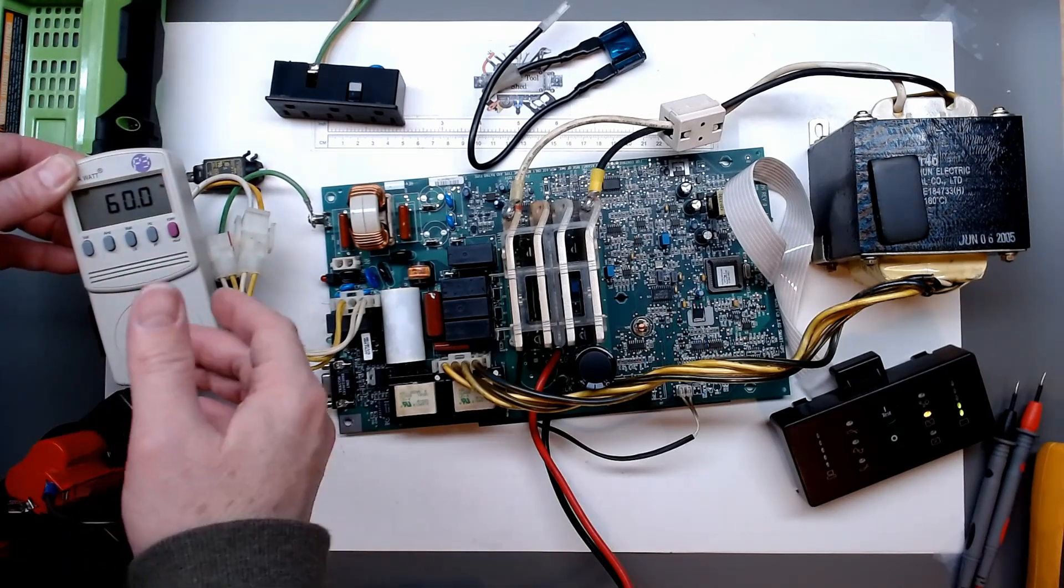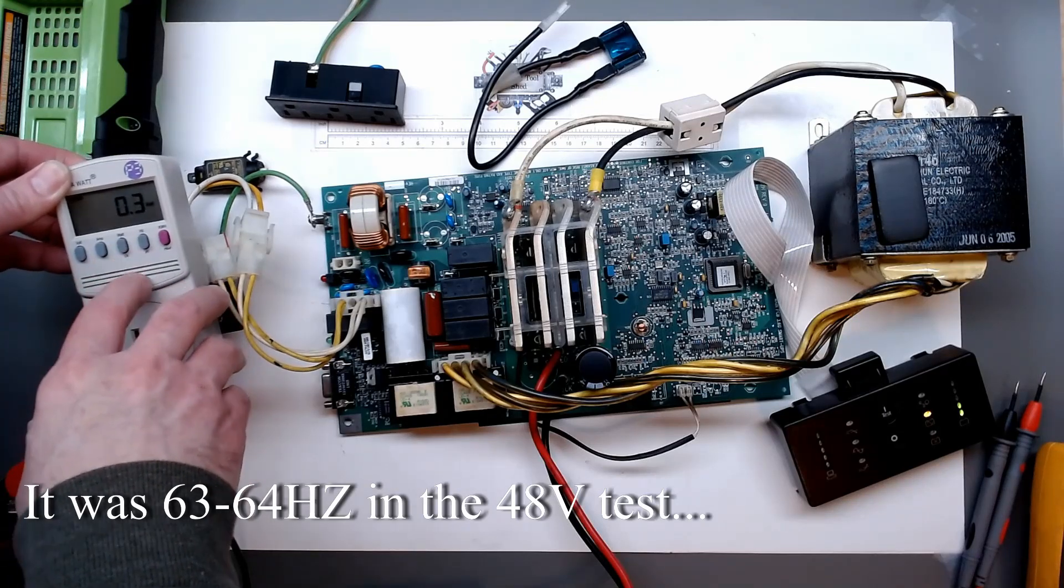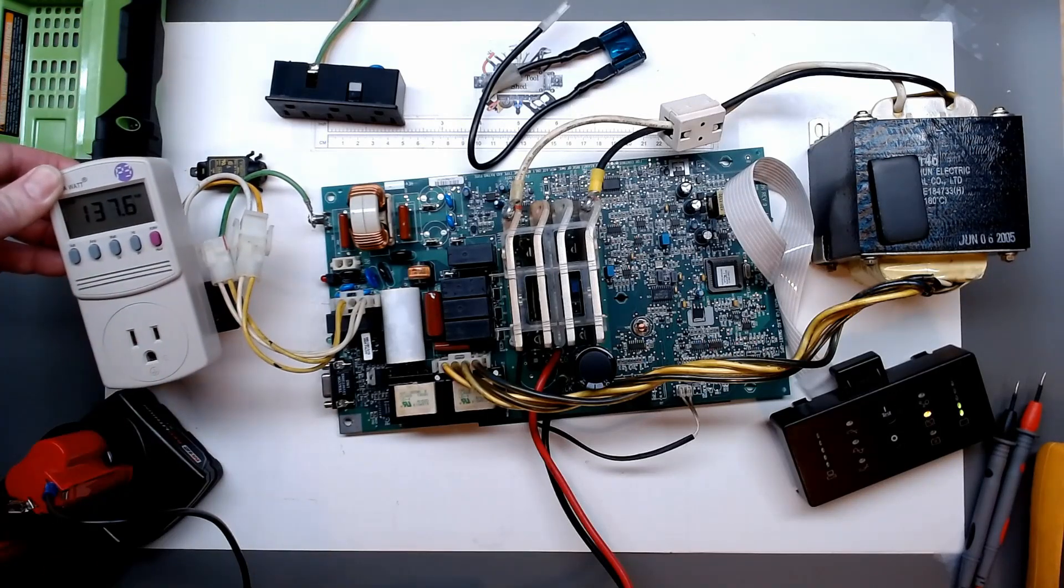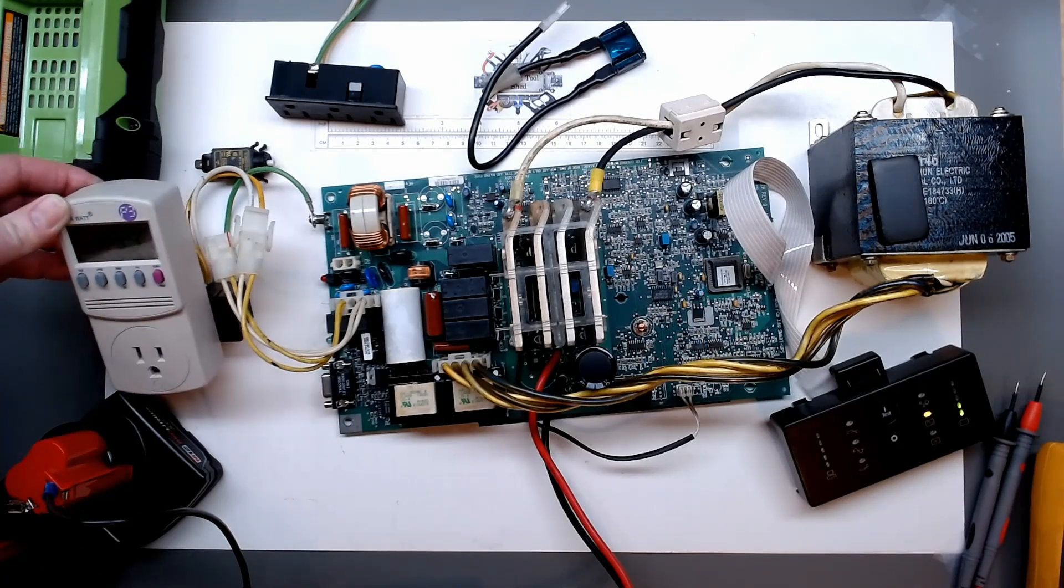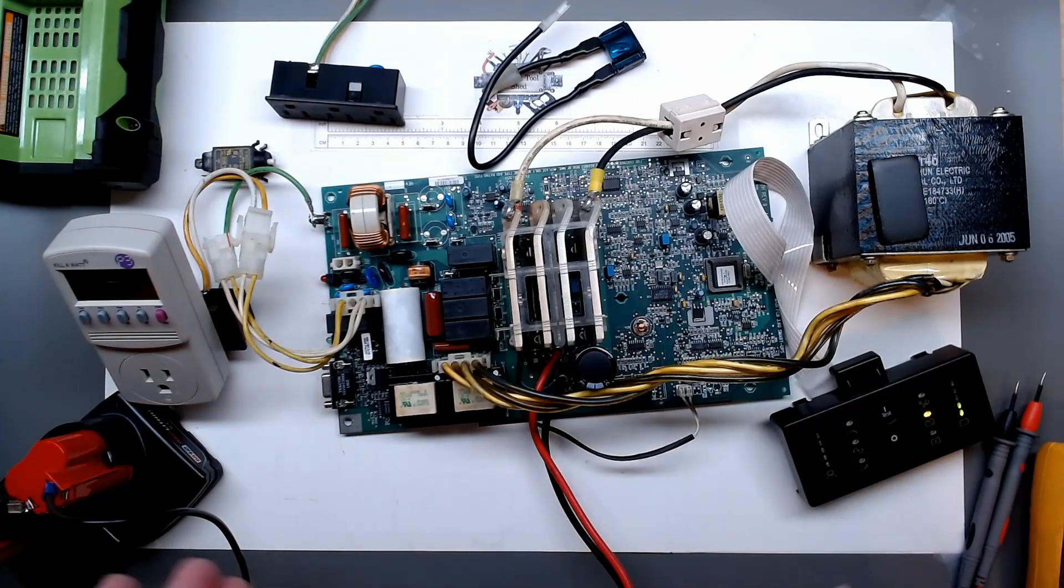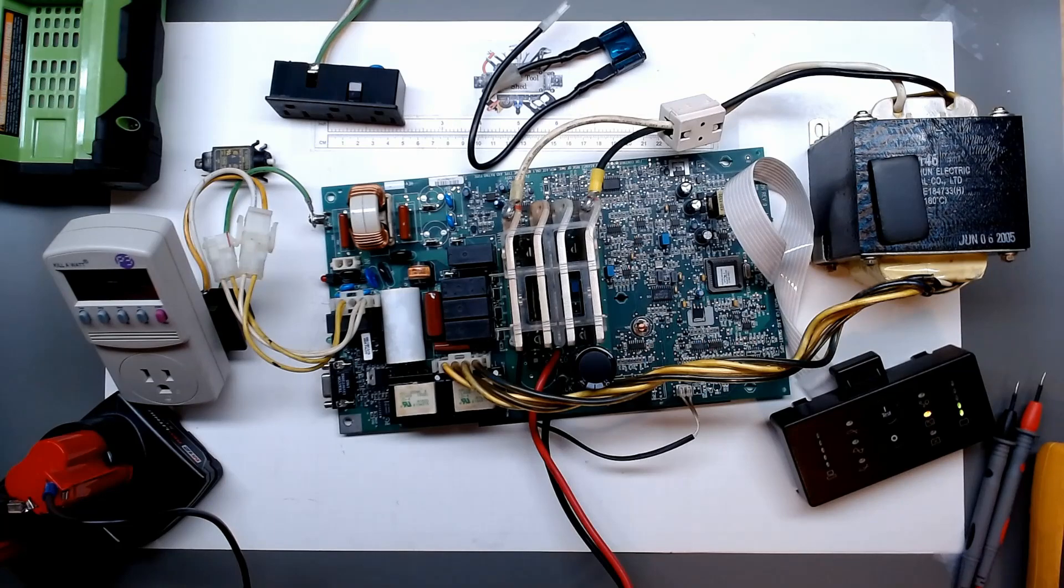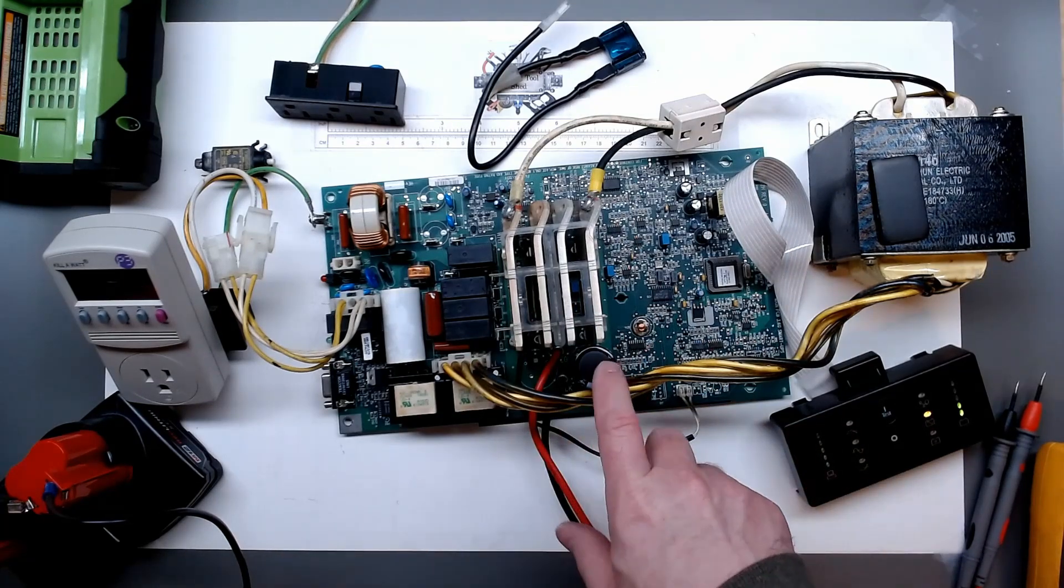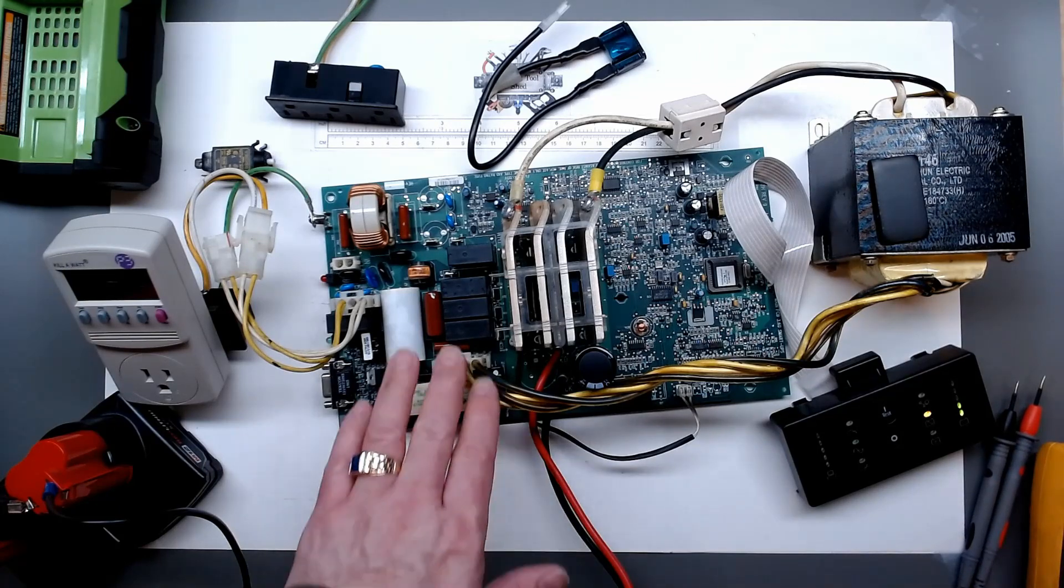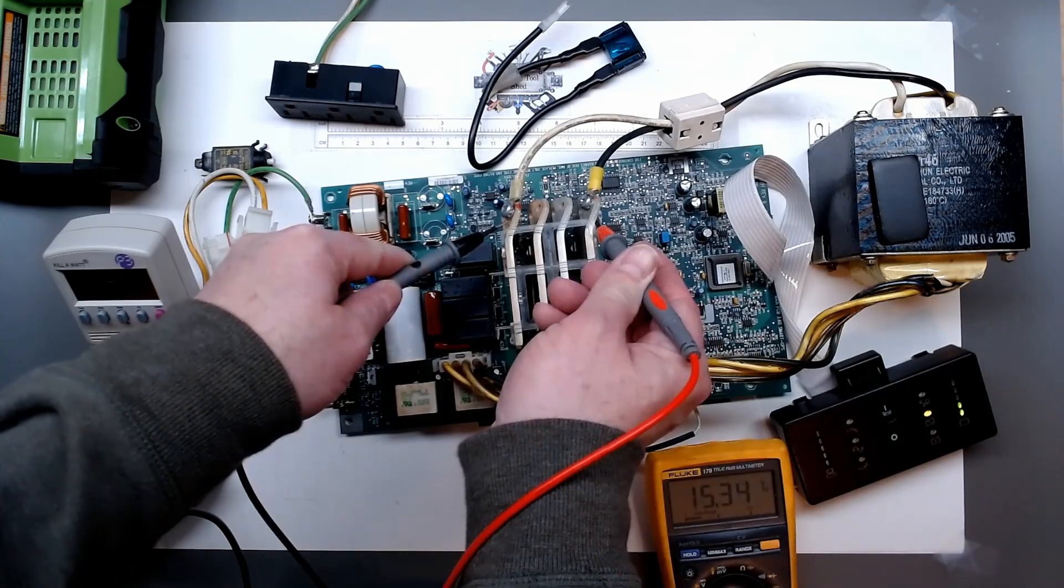Now we see our frequency is down on 60 hertz. Our voltage is around 124, 125, so I expected to be a little above 120. That's actually more about what I was expecting, but that was my failure there to forget or not mark this was a 24 volt system. I did put old volts on that cap which wasn't a good idea. I could feel the relay getting warmer, I could smell it a little bit.